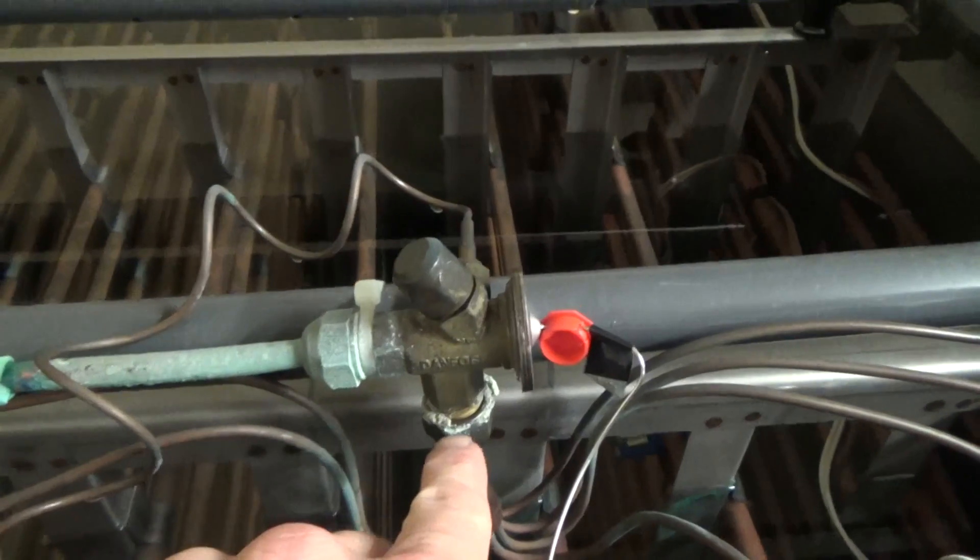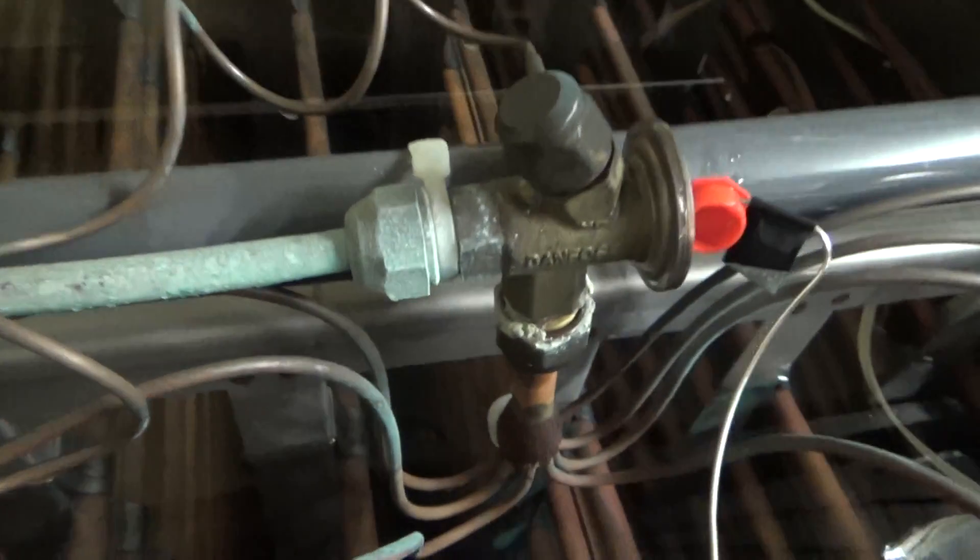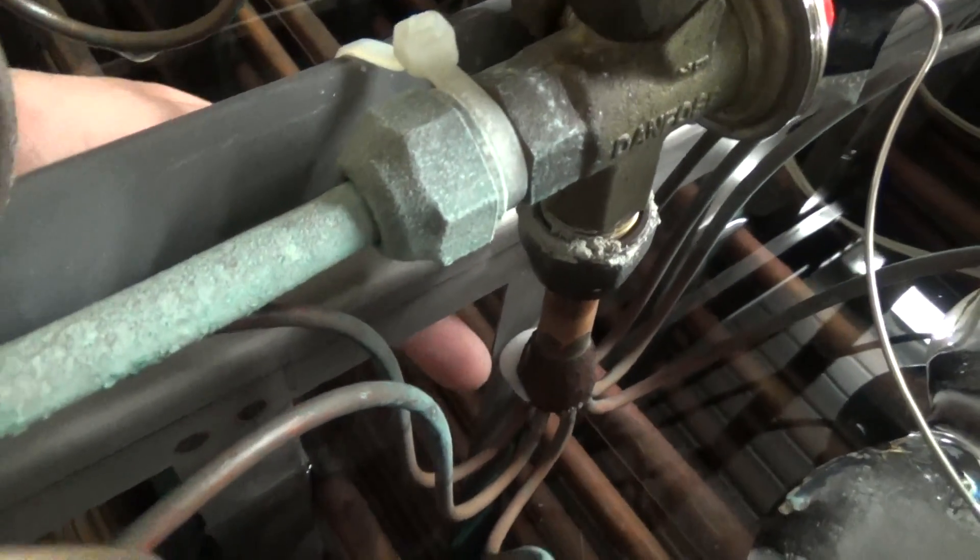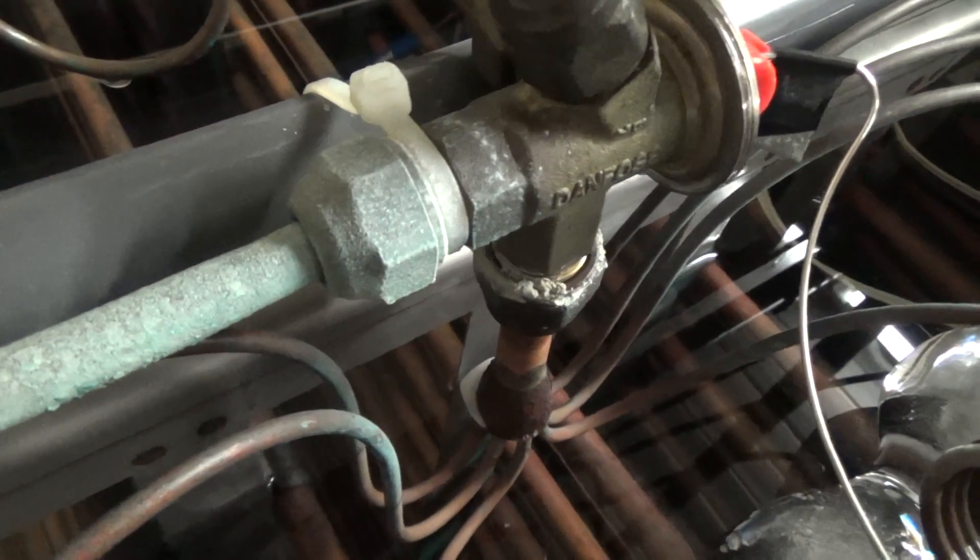I thought this one was leaking here as well because we were picking up on this one as well. But I've just spotted down the bottom there, all those bubbles growing out of the distributor there.